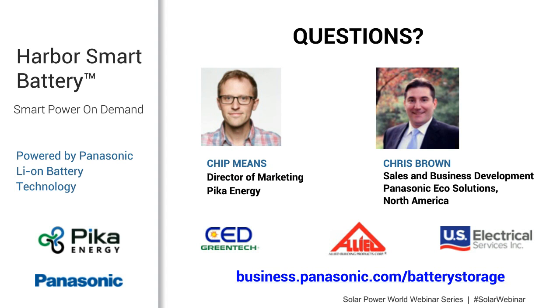Gotcha. Okay. How many Panasonic panels can connect to one PV link? That's a great question. Thank you for asking that. So in a single PV link, you can have 8 of the Panasonic modules. You would do a slightly different configuration due to the voltage on the HIT, but you would end up with 4 in series, and then another 4 in series, and parallel with a Y connector into a single PV link.